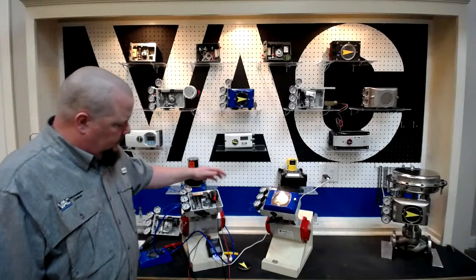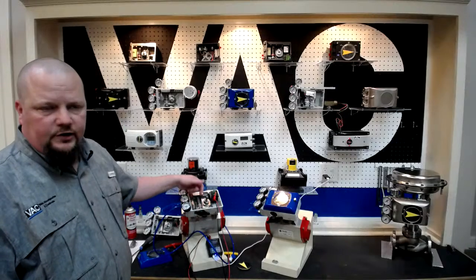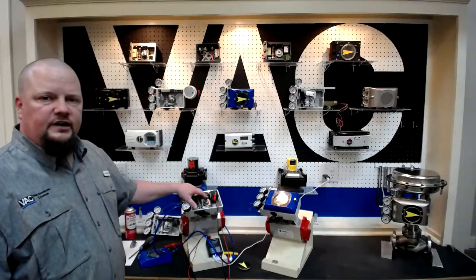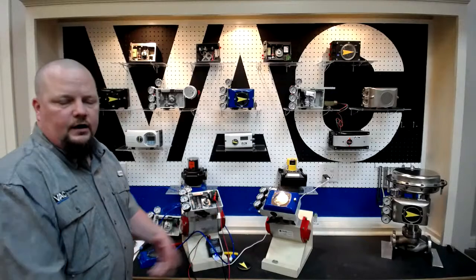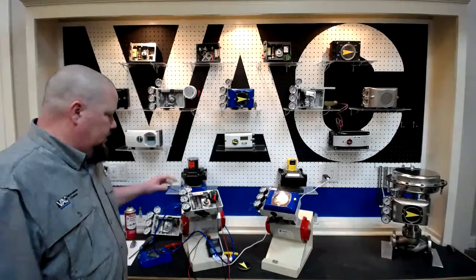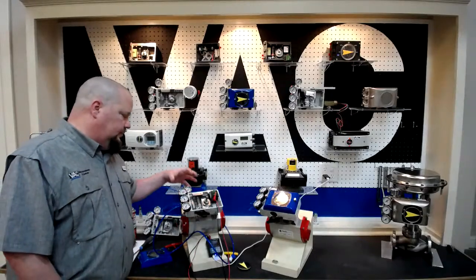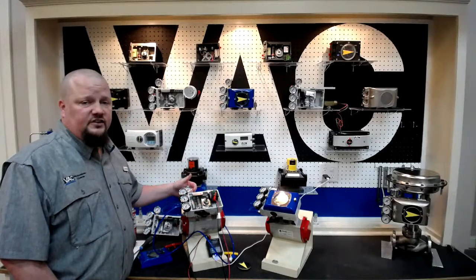Again, same thing. If this is out in the field and it's not working, the first thing you can do is pull down on that balance arm, make sure that it's pneumatically working. That will give you an idea if the actuator and valve and everything's working properly, or at least that it's tubed properly. Another large thing that is most helpful for me in the field and even on the phone when troubleshooting is gauges.